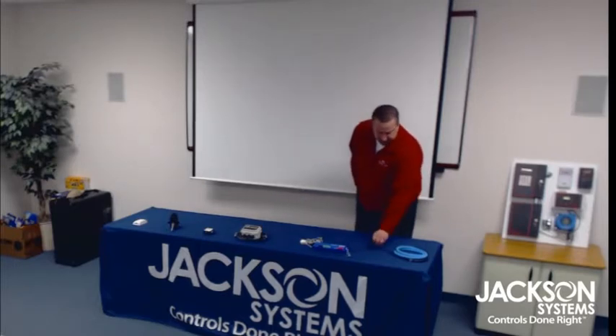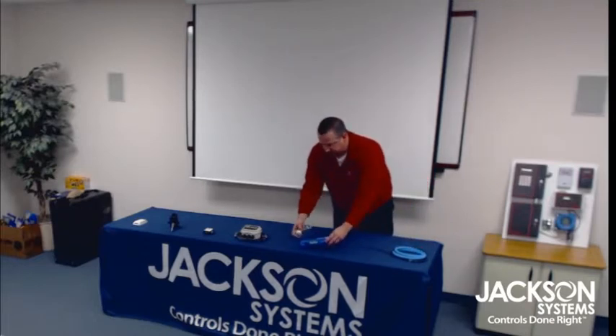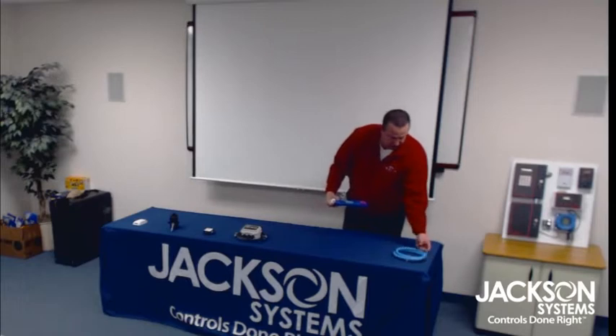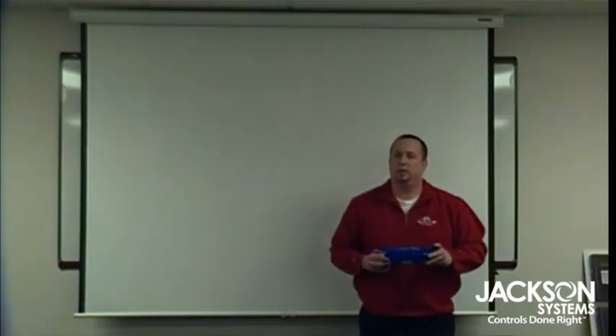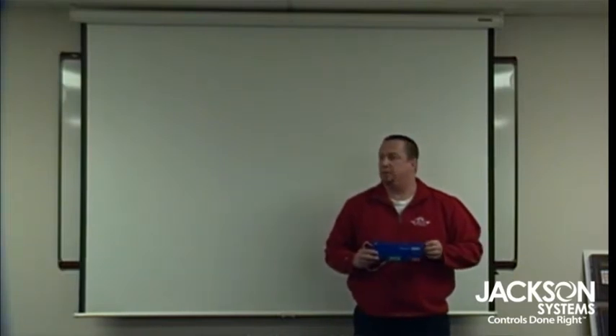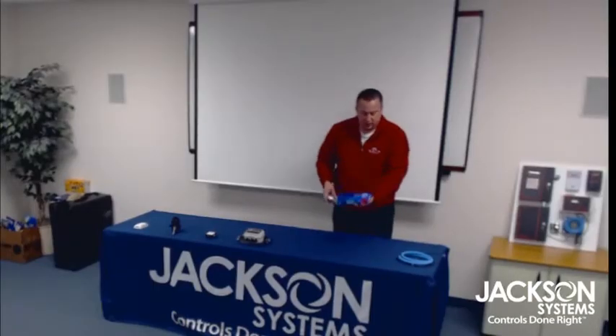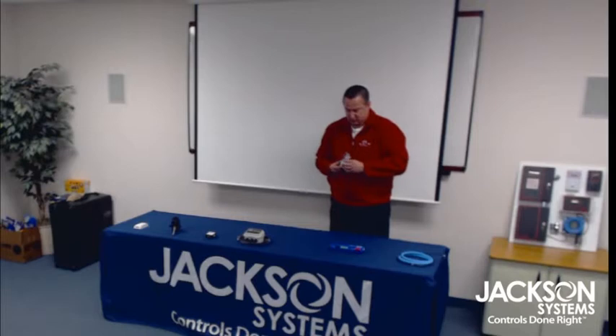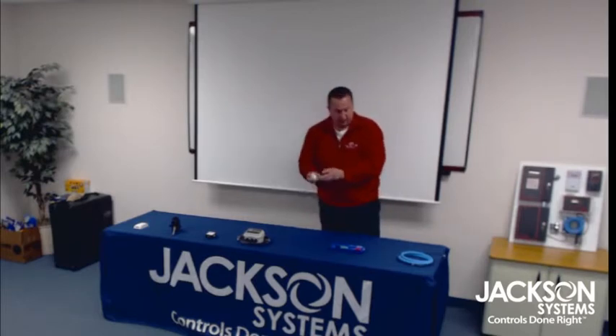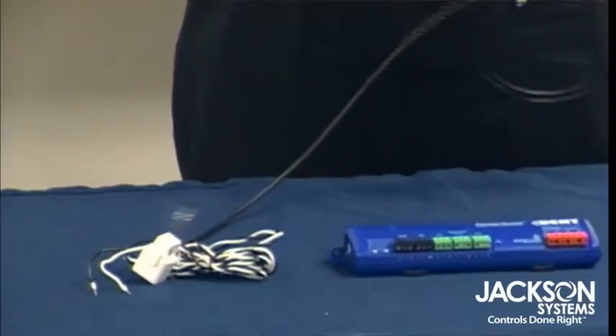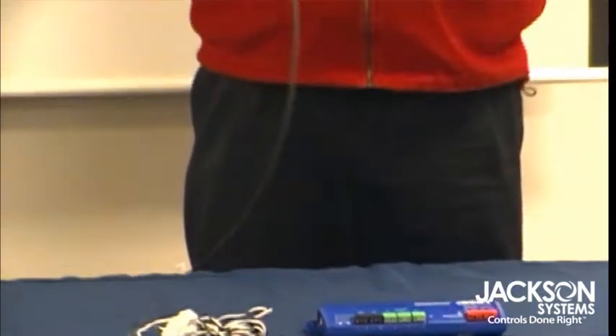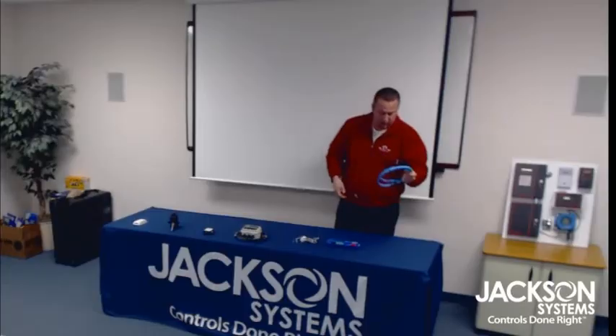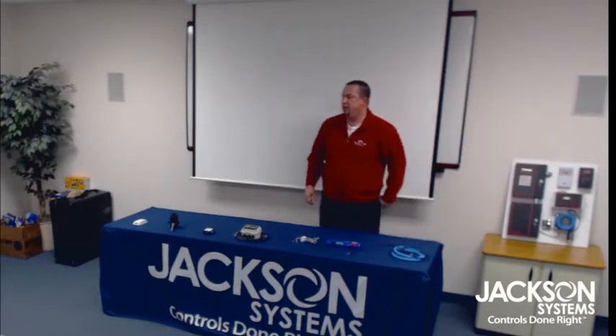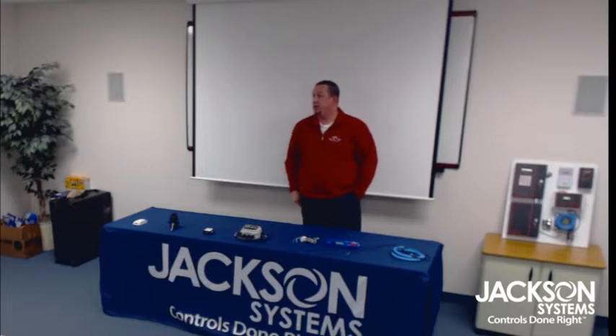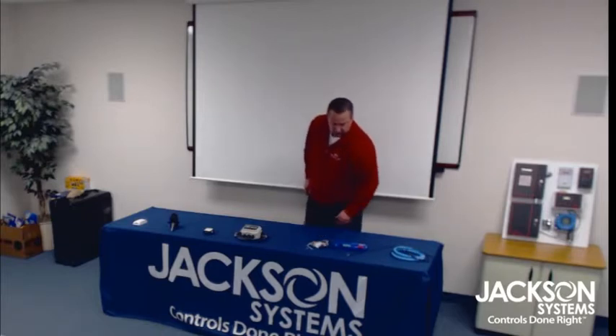systems. So first thing I'm going to show is our power meter. I was mentioning in the other class that with energy costs going up, a lot of people want a second source to really see what the amperages are, or the power, the usage of their buildings. So what these will do is just clamp on the current sensors, or CTs I should say. These are a small split core style design, and what we offer too is the rope version, which will clamp off and around and go up for the higher amperage ratings. So that's nice to have these for building owners, so they can see what maybe the power hogs are, what device you guys may need to service for them to help them save power. So that is our Power Scout, what we call kilowatt hour meters.